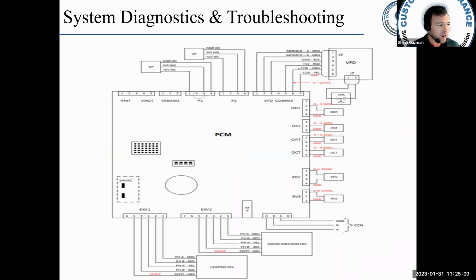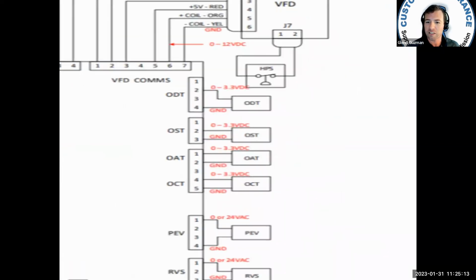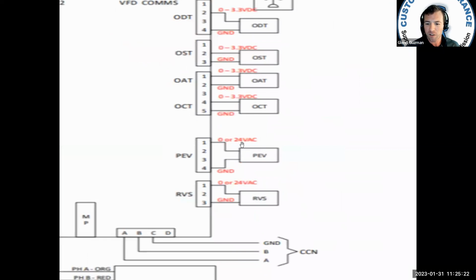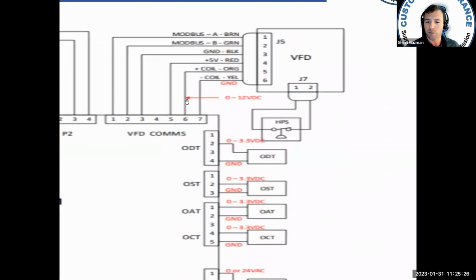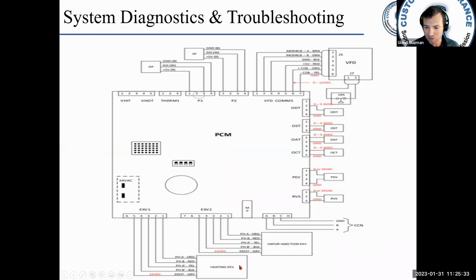I threw this one in there. It's in the back of the manual. It's pretty neat to see some of these voltage readings. If you want to know, hey, what should the voltage be on that sensor? It gives you some of that stuff. You can see the PEV, the reversing valve, 24 volts. We kind of talked about some of this earlier, 0 to 12 volts. So that one's in there. Again, it's in the back of the service manual as well. Okay.